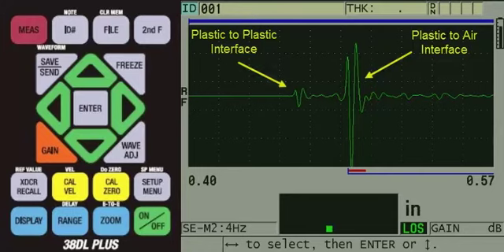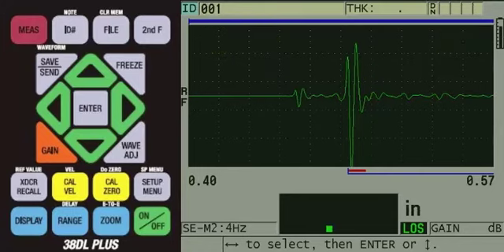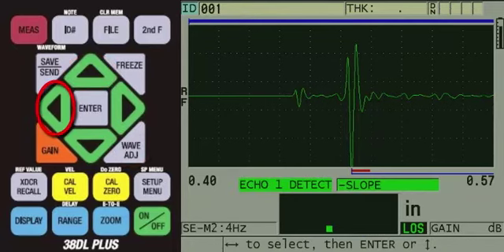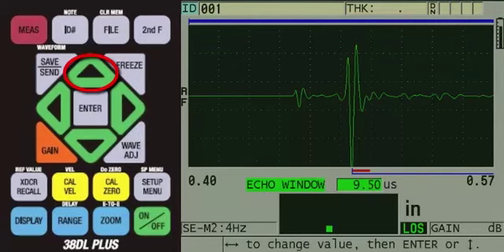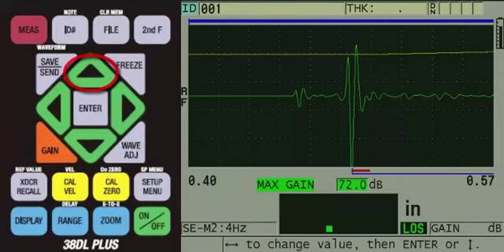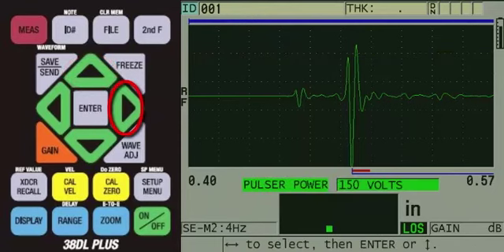The delay line echo appears negative, so we will need to change the echo 1 detection. To do this, we will press the Wave ADJ key, then we will press the up arrow to echo 1 detect, and then use the left arrow to change it to negative slope. To help increase the voltage response from the delay line echo, we will increase the voltage used to drive the transducer. To do this, press the up arrow until you get to the pulser power setting. Then press the right arrow twice to increase it to 200 volts.